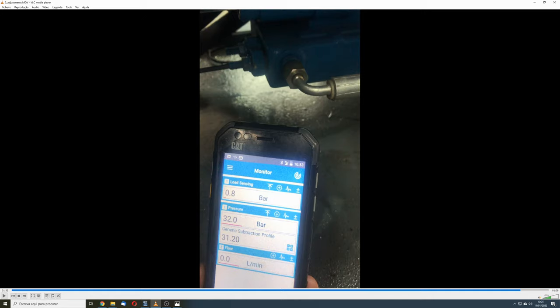Now, bullet points. Bullet point one: once again, some load sensing pumps, due to their design, can have standby higher, sometimes significantly higher than the actual delta P. It is important to know that, and it's important to understand that in such cases, your best option to check and adjust the delta P is by monitoring it directly when the pump is at mid-stroke, when the pump is pumping.